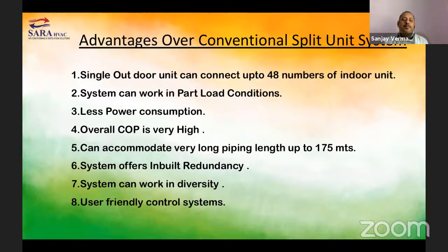And the next point is this can accommodate very long length piping, up to 175 meters. Here I am putting this as conditional - मैं इसके बाद एक और प्रेजेंटेशन स्लाइड शो करूंगा जिसमें डिपेंड ऑन फ्लोर्स, डिपेंड्स ऑन वर्टिकल, डिपेंड्स ऑन हॉरिजॉन्टल हाइट्स, the piping length varies based on that. But we can go up to a maximum piping length - this is not possible in the conventional split AC.